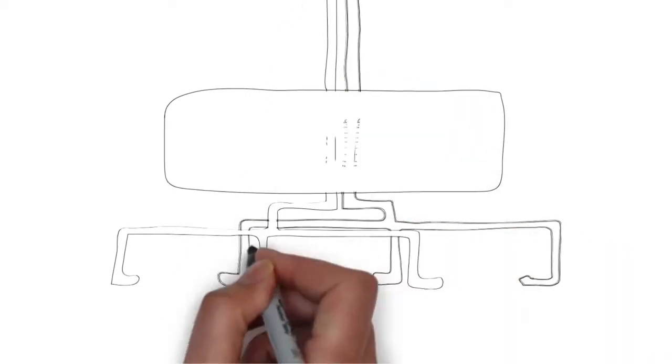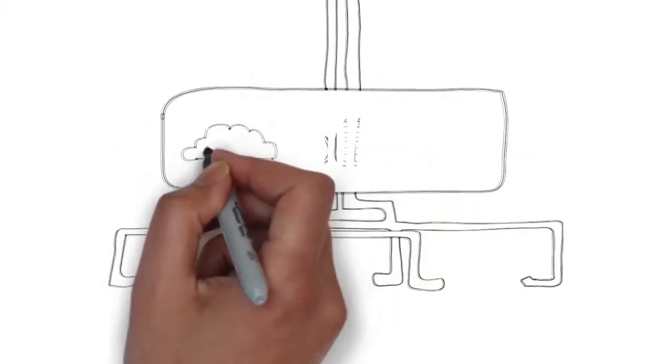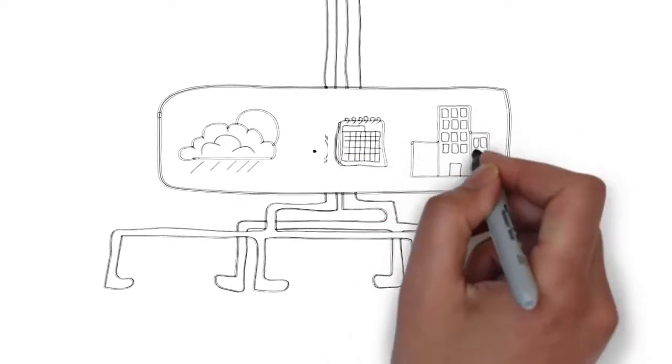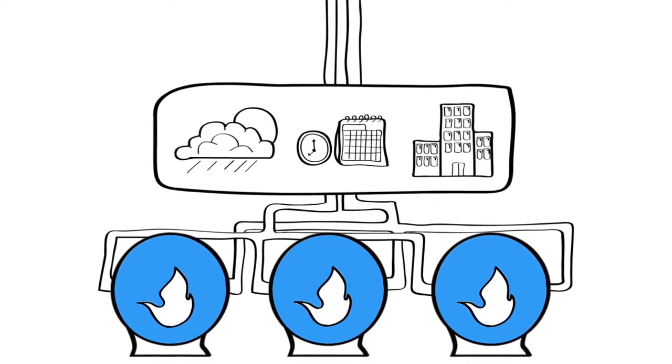Well, BMS systems, weather compensation systems and sequencing systems typically use control strategies which take measurements and control of all the boilers combined. But don't typically measure and control each individual boiler. Essentially, they macro-manage the boilers.